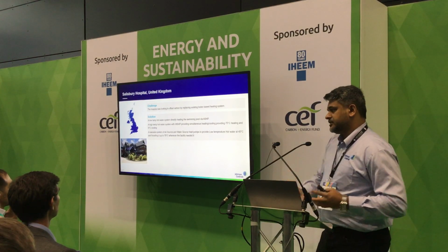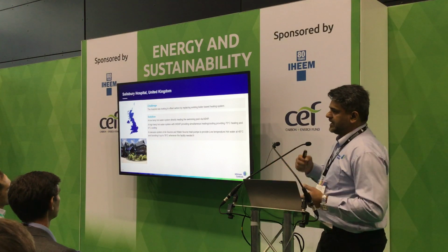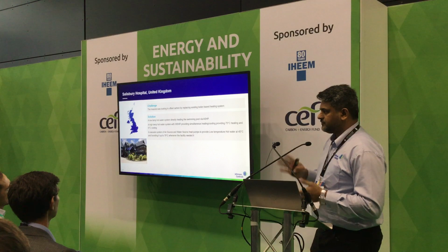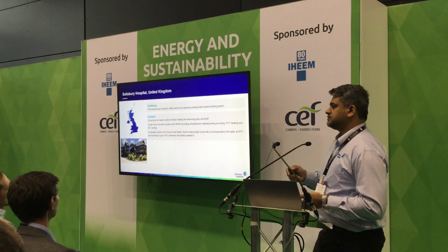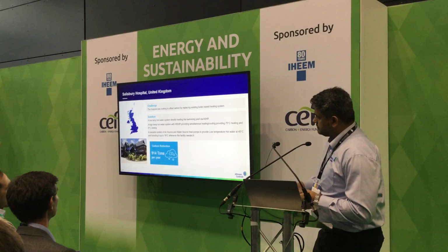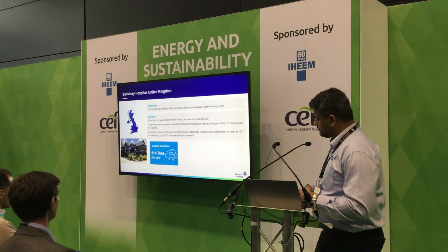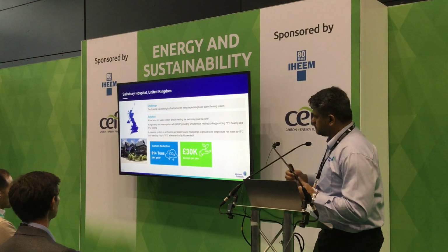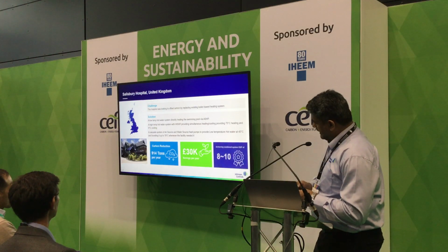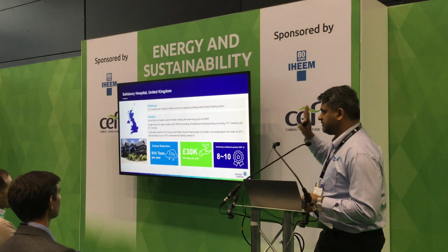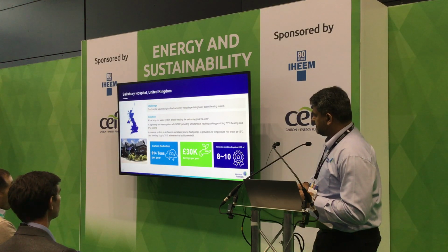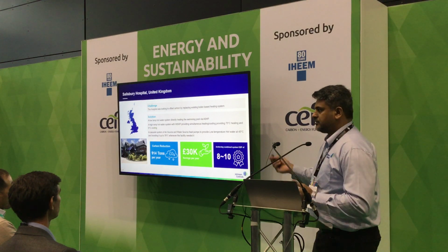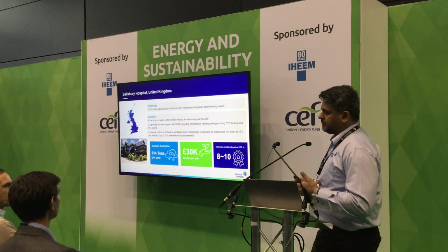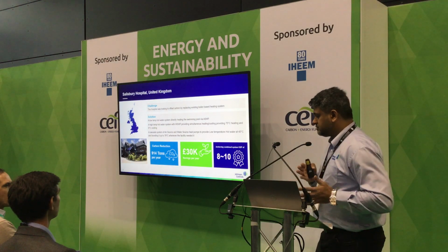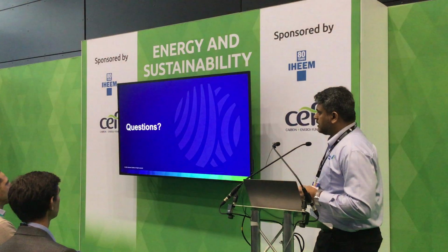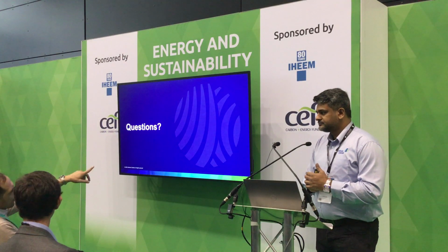Plus we used a cascade system. So an air source heat pump, a buffer vessel, and a water source. The air source would deliver the low temperature hot water system requirements of 45 degrees, and whenever required the water source would boost that up to 78 degrees. So with this, they actually achieved 914 tons of carbon reduction every year, 30,000 pounds in savings, not too much, but can't complain. And the combined system COP of this particular system implemented was in the range of 8 to 10. So at the end of the day, implementing a decarb project with heat pumps does give you savings in different avenues. Any questions?